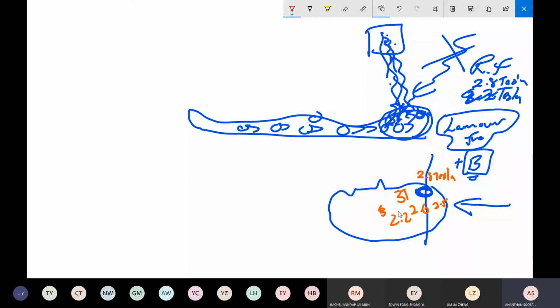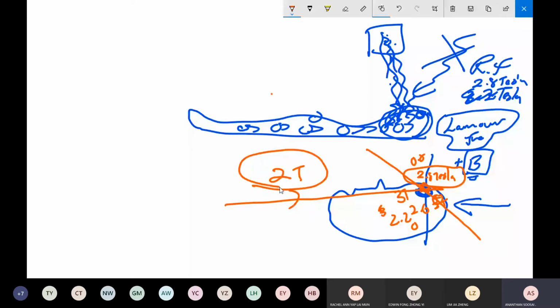So this is done by using a non-uniform magnetic field. Maybe the uniform magnetic field produces 2 Tesla. The gradient non-uniform magnetic field here applies another 0.8 Tesla, making it 2.8 Tesla at this point. It's called gradient coils. Gradient coils make it 2.8 Tesla here, increasing the magnetic field strength. The magnetic field strength at every specific point is actually the combination of the magnetic field strength of the uniform magnetic field plus the magnetic field strength of the non-uniform magnetic field.